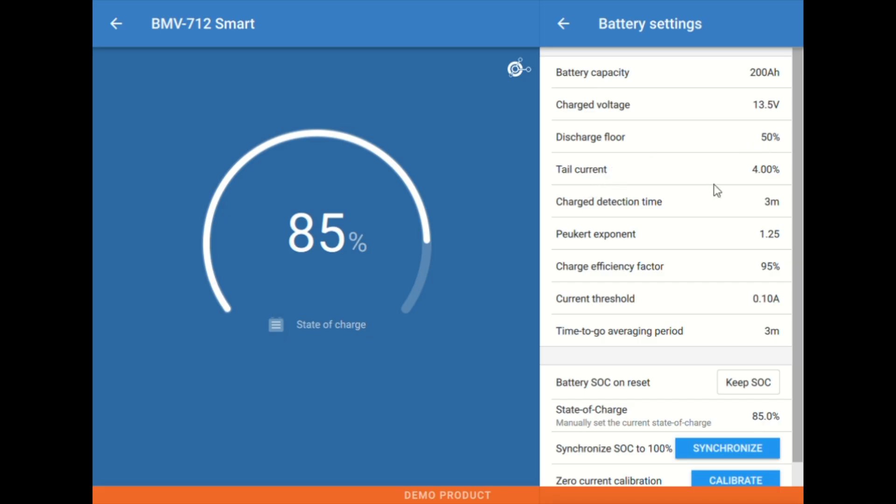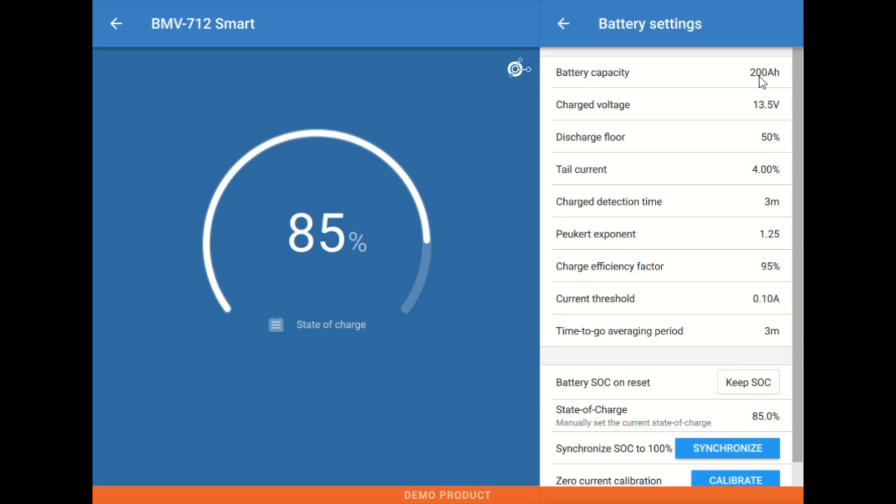Next up we have tail current. Tail current is a percentage number of amps moving through the system. It's a signal to the meter that the batteries are full essentially and they're no longer taking current. So the quick way to look at this is this is 4% in amps of your battery capacity.